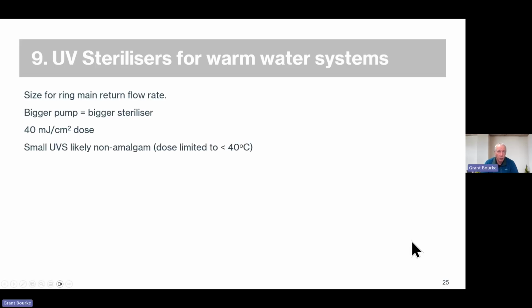So small systems for your domestic houses, sort of with half-inch connections, are likely to have a non-amalgam bulb. Larger ones will have an amalgam bulb, and they're good to higher temperatures because the amalgam bulbs regulate the vapor pressure inside the lamps, and they aren't affected as the temperature gets higher. The smaller ones don't do that. So the dose is usually specified in smaller systems at 40 degrees.